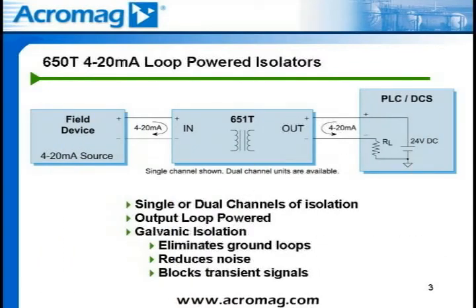Two-wire isolators fit applications where an isolator is required and a power supply is in series with the output signal. The 651T and 652T transmitters and the 653T signal splitter provide input to output isolation and are output loop powered, which means 12 to 50 volts DC is provided by a power supply on the output loop.